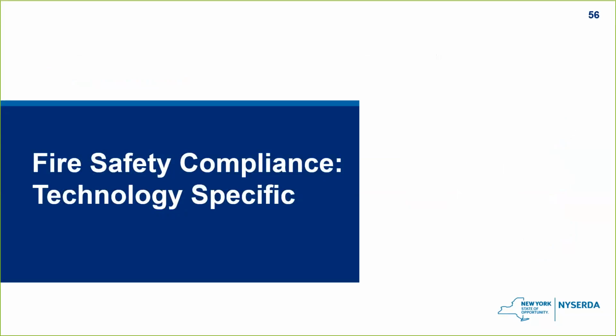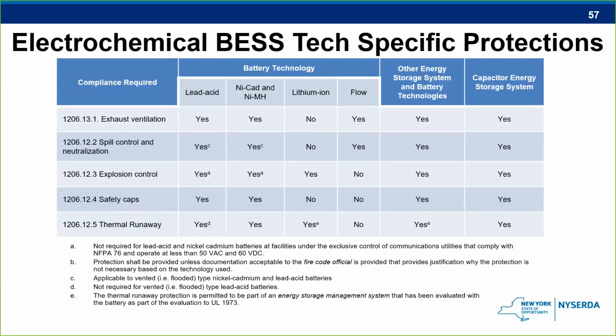Okay, so we just covered a lot of requirements for some commercial systems. Most of these are put in place to prevent thermal runaway. And now we're going to talk about different requirements necessary based on different battery technologies. They're not all created equal, and the different chemistries lead to different compliance that's required to maintain safety. So this table here is showing an example of the types of charts you'll see in the code. This one lists out the battery technology and shows which protections are needed for specific chemistry types. As they differ, there are different requirements for each chemistry based on the types of hazards they might cause.